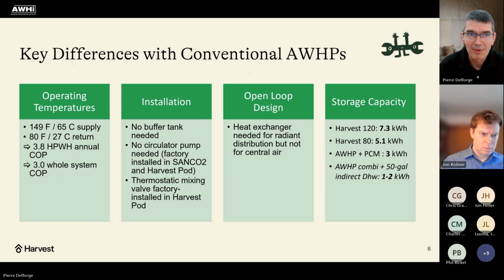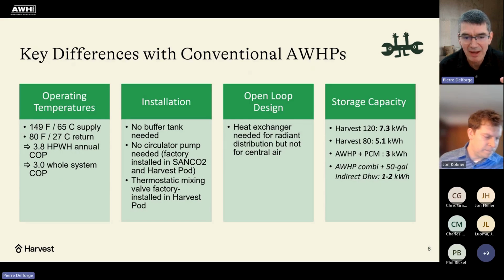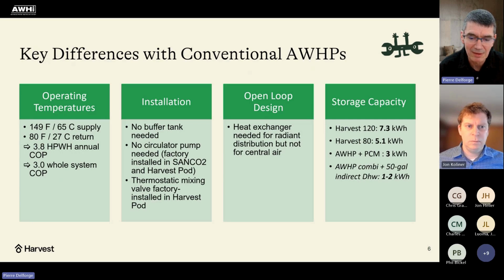So we use external heat exchange. Sorry for going maybe too much into the weeds here, but we do external heat exchange to be able to keep stratification at all times and never mix the tank. So the whole system is designed to keep the tank stratified as much as possible. Just to give you a sense, I don't have a picture of it, but you may have the top third of the tank at, let's say, 145, 150 degrees, and then a pretty sharp thermocline of just a couple of inches, and then water at 80, 85, which is return temperature water, and then water at 40 or 50, which is domestic hot water makeup water, and that all stays stratified. The water that's returned to the heat pump is from the bottom of the tank. So you return the coldest water to the heat pump, bring it back up to 150 in a single pass, and put it at the top of the tank.